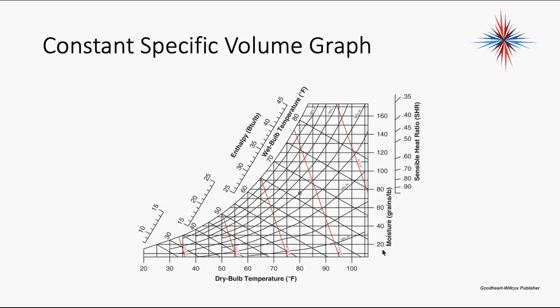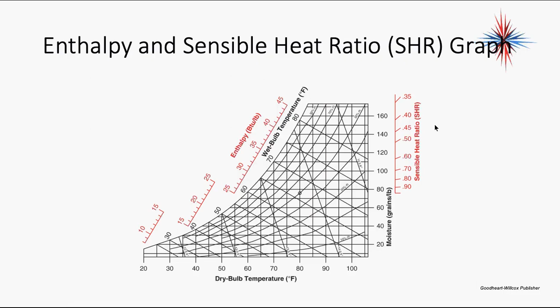Enthalpy and sensible heat ratio, you just extend the various lines and you can find my enthalpy, which is how much heat is totally in the air, including moisture, and what percentage of that, or what the ratio is, of sensible heat. Remember, sensible heat is heat I can measure, heat I can take out and put in without changing the moisture content of air. So that becomes pretty important when we talk about humidification and dehumidification.